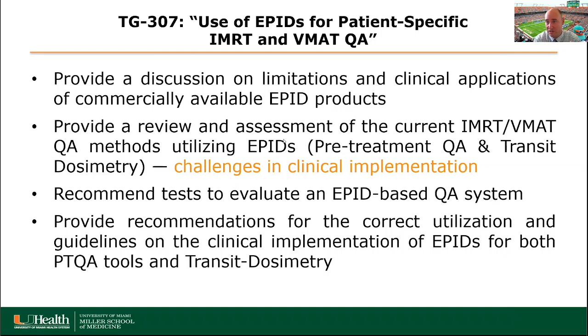So error detection sensitivity. This is important. It's probably important for every single in vivo dosimetry technique that's out there. It's important to understand what level of error that you can detect with your system. And so one aspect of the task group report is where we recommend you take existing plans and you introduce known errors to it of different magnitudes, and things like MLC positioning or patient thickness changes. You can step up the amount of induced error, and then you can start to dial in exactly how sensitive your software solution, your EPID solution is at picking up on these issues. It's a really complicated topic, so it's all in the task group report if you want to read more.